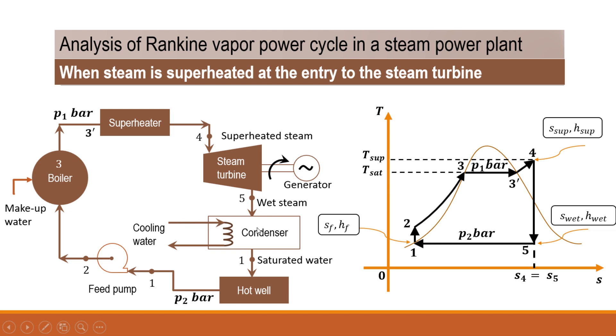The wet steam enters the condenser where vacuum is maintained and cooling water is circulated. In the condenser, latent heat is absorbed from the wet steam, converting it to saturated water — only a phase change takes place, from vapour to liquid, at constant temperature. That saturated water is stored in the hot well and from there, at lower pressure, it is pumped by the feed pump back to the boiler at higher pressure.